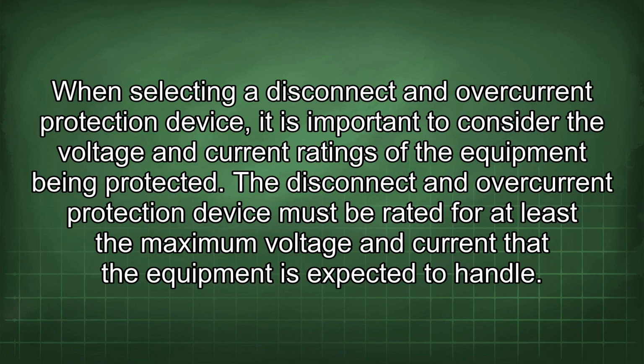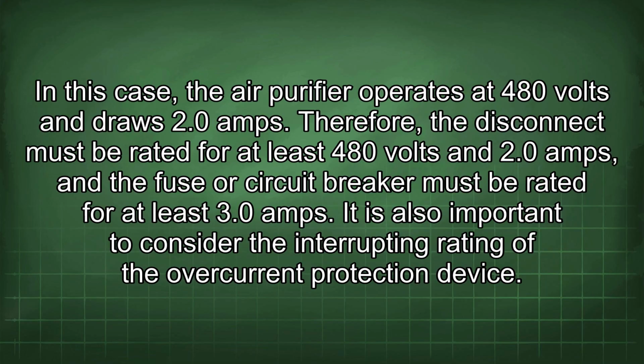When selecting a disconnect and overcurrent protection device, it is important to consider the voltage and current ratings of the equipment being protected. The disconnect and overcurrent protection device must be rated for at least the maximum voltage and current that the equipment is expected to handle. In this case, the air purifier operates at 480 volts and draws 2.0 amps. Therefore, the disconnect must be rated for at least 480 volts and 2.0 amps, and the fuse or circuit breaker must be rated for at least 3.0 amps.